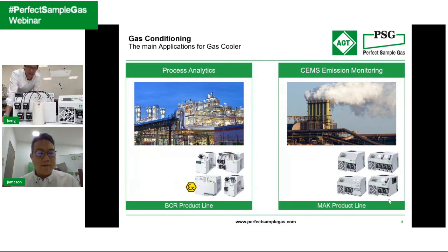Well, I think fundamentally, for a process cooler, we are able to take positive pressure. And secondly, not just because of how high the positive pressure is, but rather, the positive pressure we can handle with stainless steels like this, but the response time, the speed, matters. We can take higher flow rate. When we take higher flow rate, we want the fresh sample rather than the lag sample. We need this fresh sample to come into the sampling system to reach the analyzer in the shortest time, so that the analyzer can respond in the control.